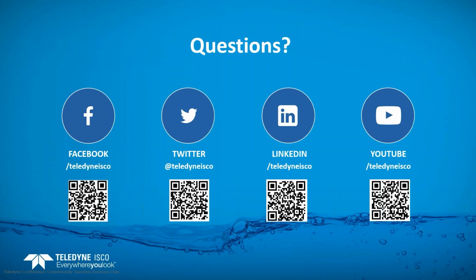Any possibility of powering the sensor using solar energy? Actually, yeah, the solar energy and the battery it's used with is on the outside. Now, this would only work if the sensor's on the outside in the safe area. Obviously, with the intrinsically safe DuraTracker being down inside the manhole, those would be battery only, the lithium and the D cells, like Daryl mentioned. But if you have it set up for the signature being outside in the safe area, if the unit is in the safe area, then we can power it up with the solar panels there. You still have your barrier block that you hit before it goes down into the manhole where your sensor's at. So yes, solar power would work as long as it's an application where the meter is in the safe area. If we have the DuraTracker down in the hazardous location, obviously no, we can't. We'd have to use batteries only.